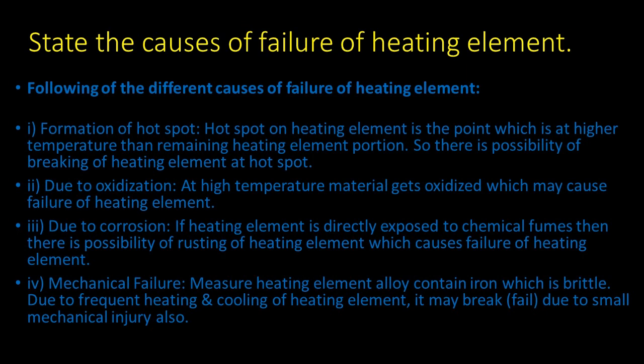Mechanical failure. Most heating element alloys contain iron, which is brittle. Due to frequent heating and cooling of the heating element, it may break or fail due to small mechanical injury also.